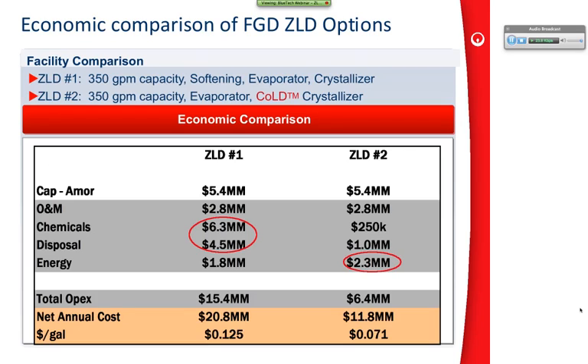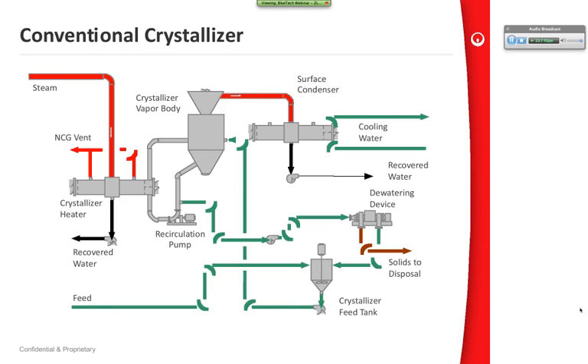Here's just a really quick comparison of 350 gallon a minute ZLD systems, one using softening plus evaporator plus crystallizer for FGD, sort of the system that Dan showed you before in Italy. This compares to a same capacity system using the cold crystallizer. You can see that the system requiring softening uses a lot of chemicals and generates a lot of solids for disposal. Even though the energy requirements are higher for the cold system, the bottom line is much, much less because we eliminate those chemicals and so forth. This is a conventional crystallizer.